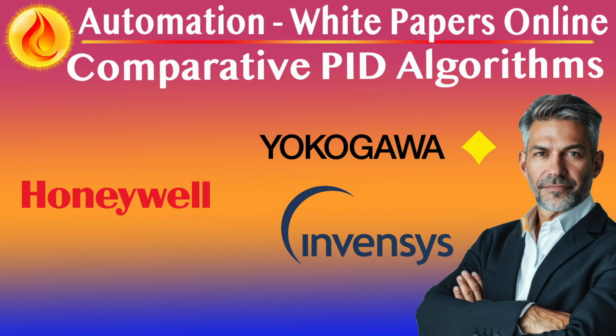Yokogawa uses a combination of ideal, interacting, and parallel, non-interacting PID forms. While the ideal form offers predictable and intuitive tuning behavior, the parallel form gives users independent control over P, I, and D terms. However, this independence introduces nonlinear interactions. Changes in controller gain affect the effective strength of both integral and derivative actions. This makes the tuning response less intuitive, particularly in loops involving derivative action. In summary, Honeywell simplifies loop behavior through predefined PID modes, whereas Yokogawa offers more engineering flexibility at the cost of greater configuration responsibility.